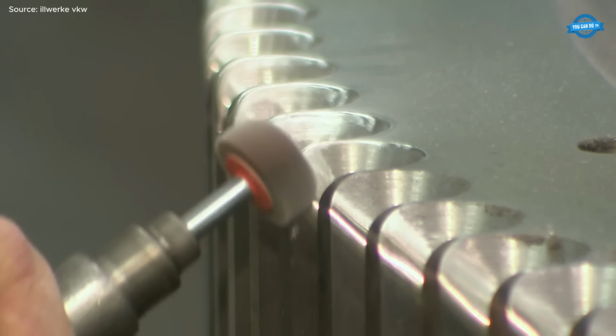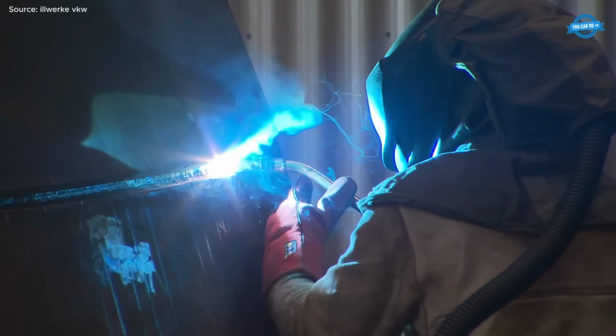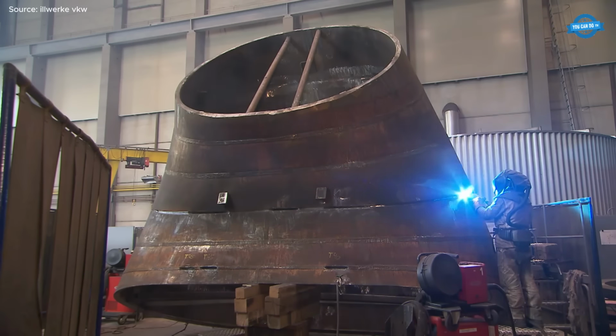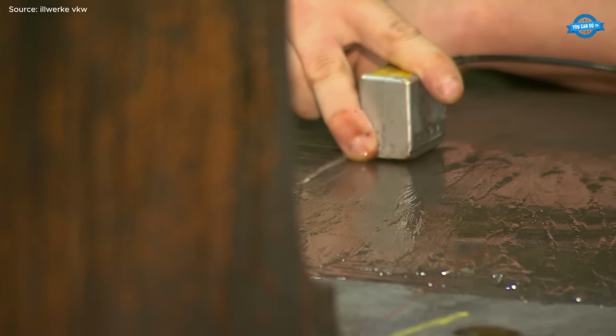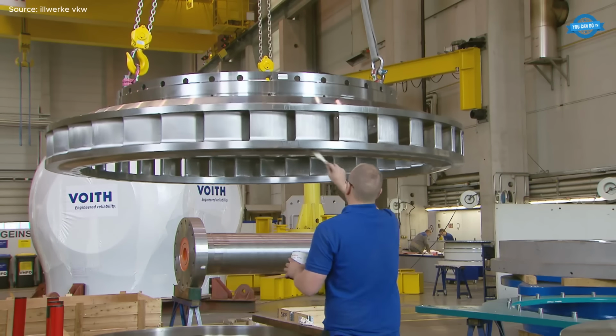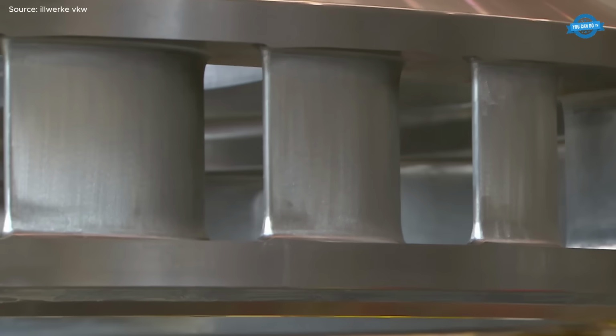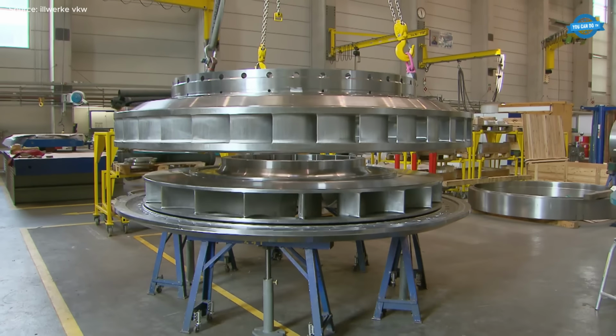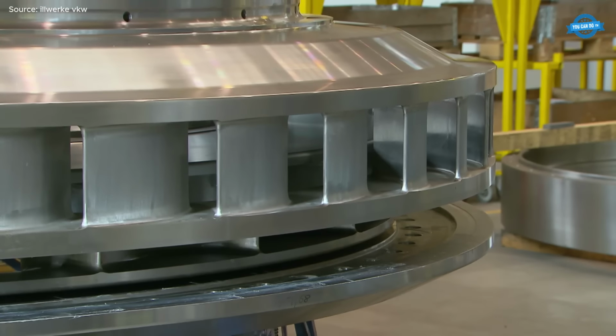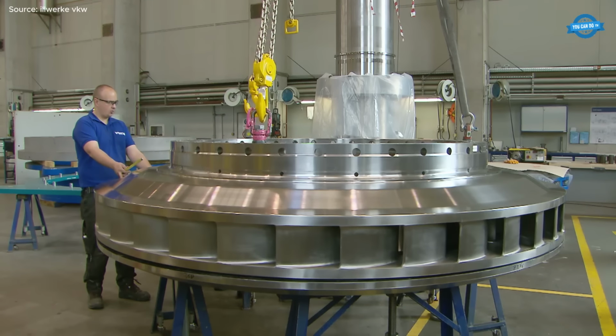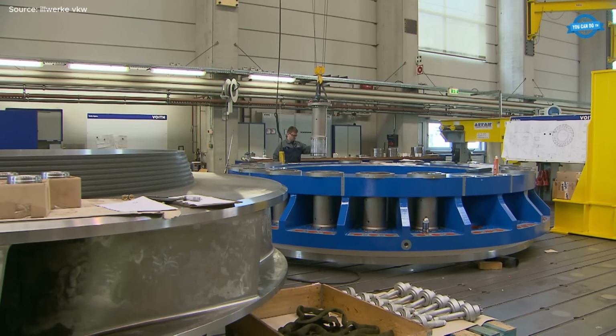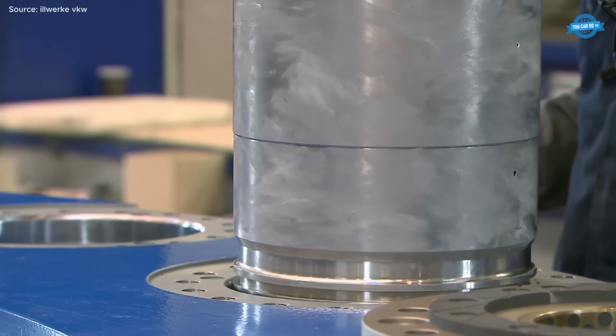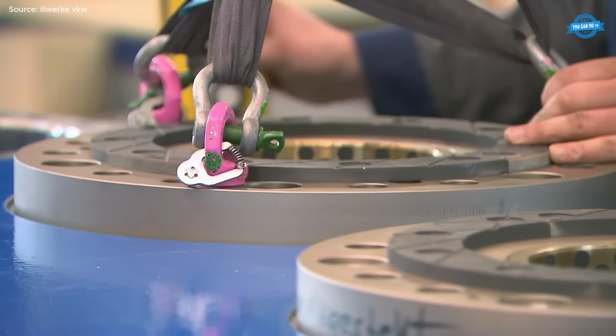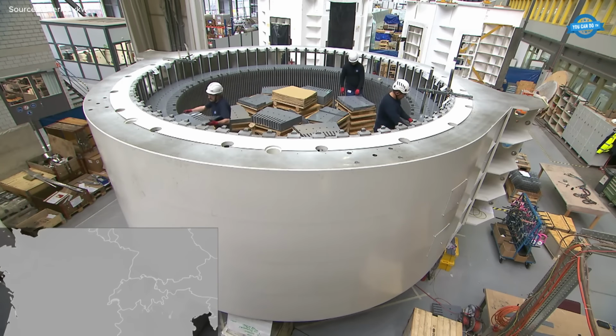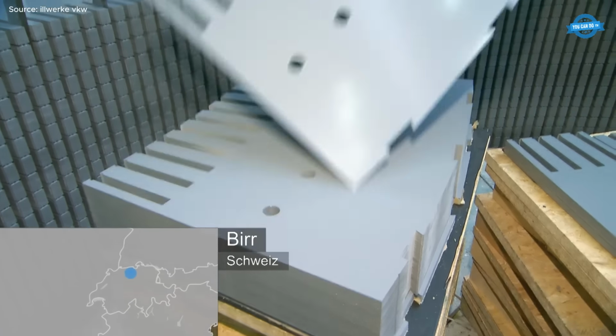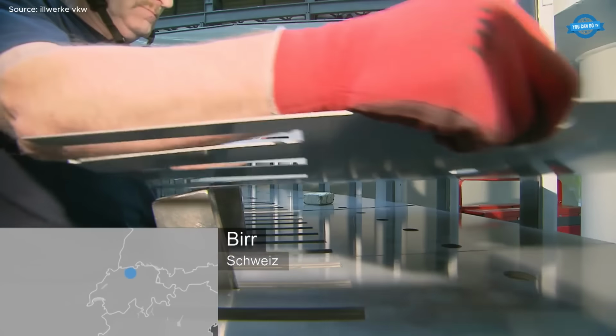At the lower end of the Silvretta pressure shaft, workers spent 5 months assembling the Hosenrohr, or distribution pipe. This Y-shaped massive steel structure splits the water flow from the main shaft into the 2 separate machine units. Piece by piece, these steel sections were transported into the mountain and welded together with absolute precision. Once finished, this vital component was encased in meters of concrete, hidden forever from view, accessible only to inspectors during future maintenance.